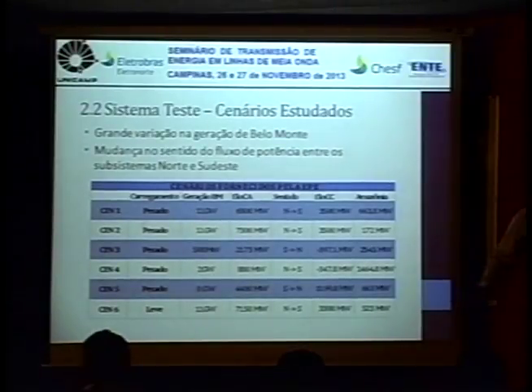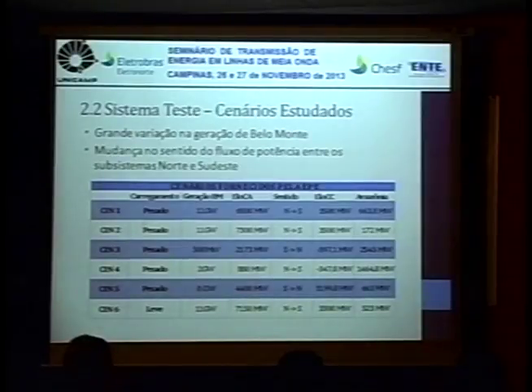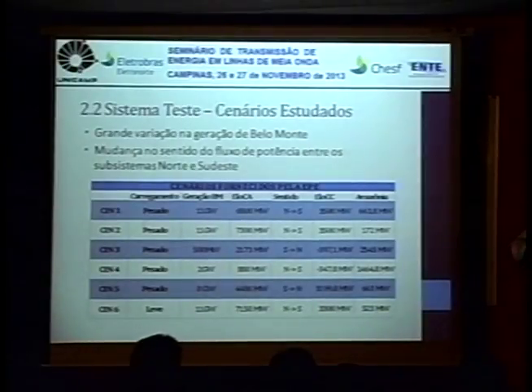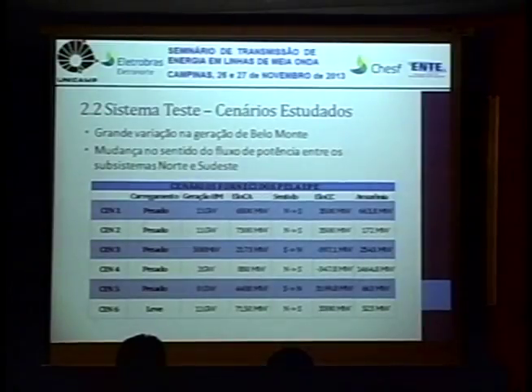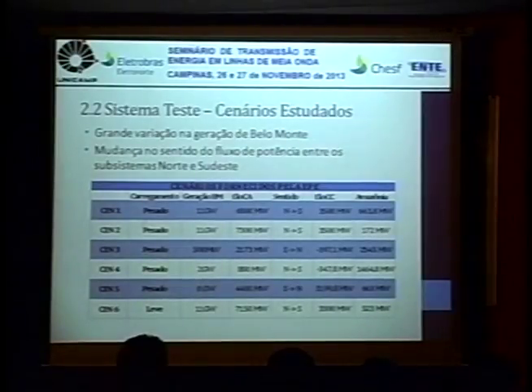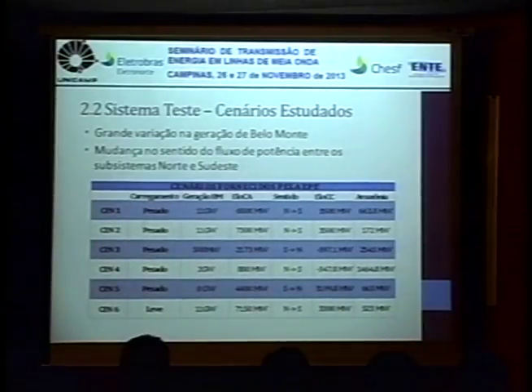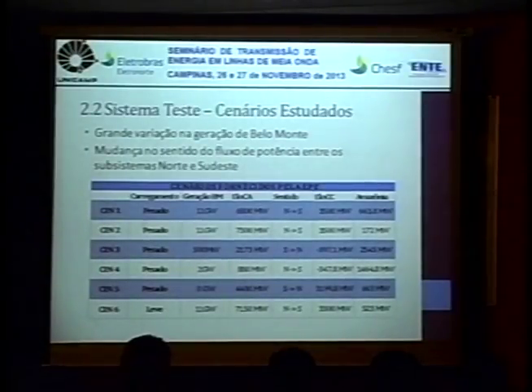So in this critical scenario, something that came about was the efficiency of the line. The losses would be gigantic, especially in situations of light load in the line. In the situations where the load would be closer to the characteristic power, the report from EPE showed efficiency of 16, 20, maybe 18%. So this is a challenge that Professor Maia Cristina brought to us: to study this case and see if we could improve this performance level, especially in terms of efficiency of the line, to improve the losses. So this was the purpose of this master's thesis.